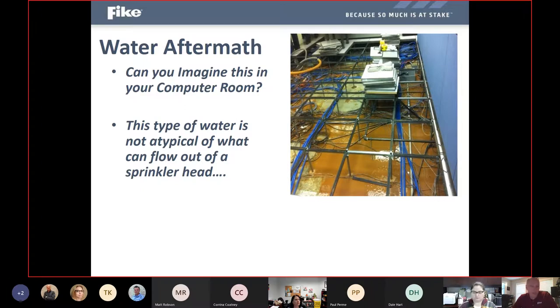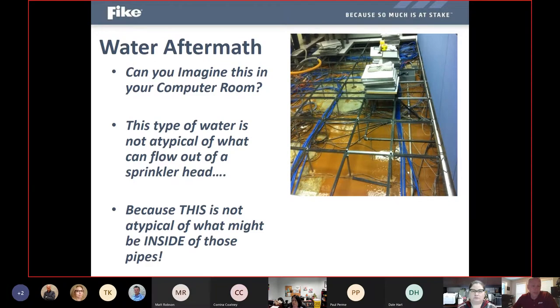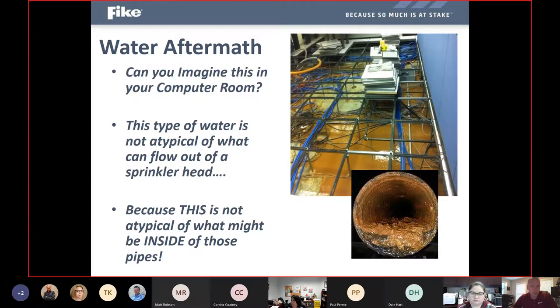And we know that the water that comes out of a sprinkler head, at least initially upon discharge, is usually not the cleanest, because there is a phenomenon that will occur in sprinkler pipes with that corrosion and that what's called MIC buildup inside those steel pipes from the presence of water and oxygen inside those pipes over a prolonged period of time. So not only do the sprinkler pipes potentially risk being reduced as far as the efficiency and the amount of water they can flow through them because of that buildup of that corrosive material over time, but it could also clog up a head and prevent a head from potentially discharging when it needs to. But the water that does come through is going to contain that and be pretty murky and muddy and not smell the most pleasant. So there is quite a bit of cleanup that's going to be associated after any sprinkler head ever discharges.